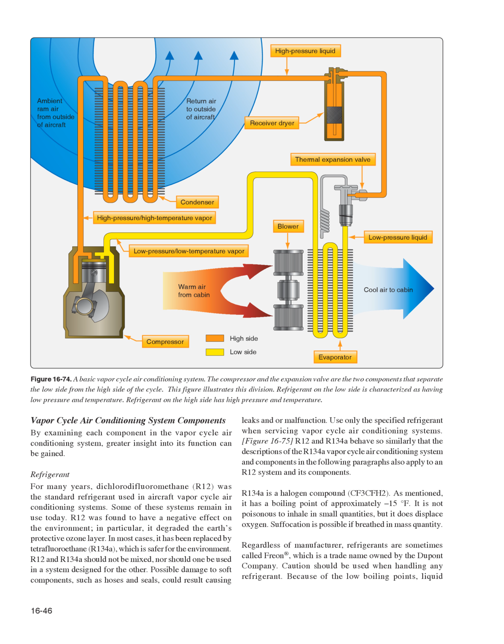R134A is a halogen compound, CF3CFH2. As mentioned, it has a boiling point of approximately -15 degrees Fahrenheit. It is not poisonous to inhale in small quantities, but it does displace oxygen. Suffocation is possible if breathed in mass quantity. Regardless of manufacturer, refrigerants are sometimes called Freon, which is a trade name owned by the DuPont company. Caution should be used when handling any refrigerant.